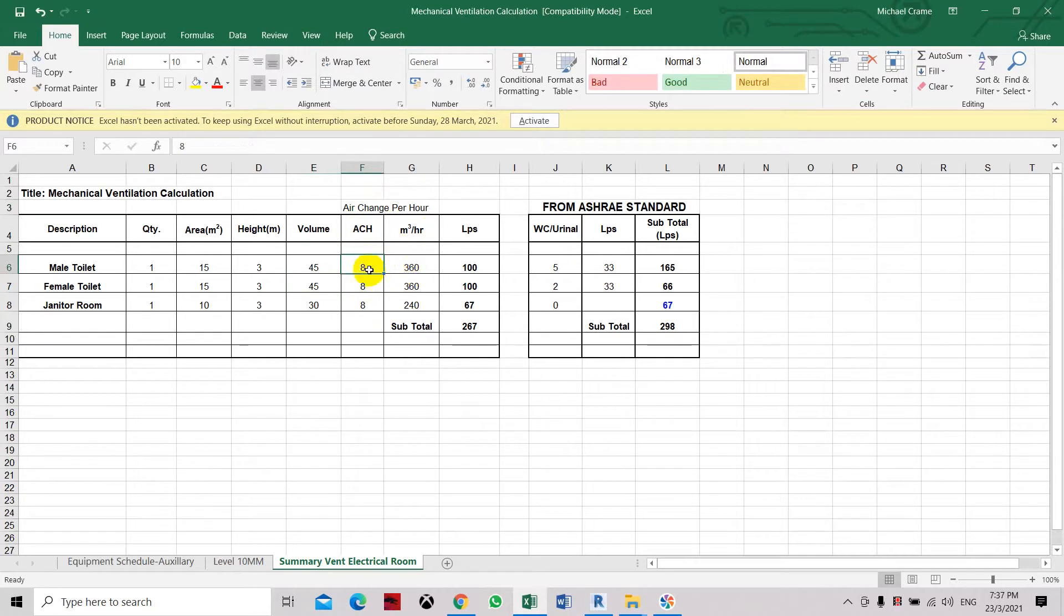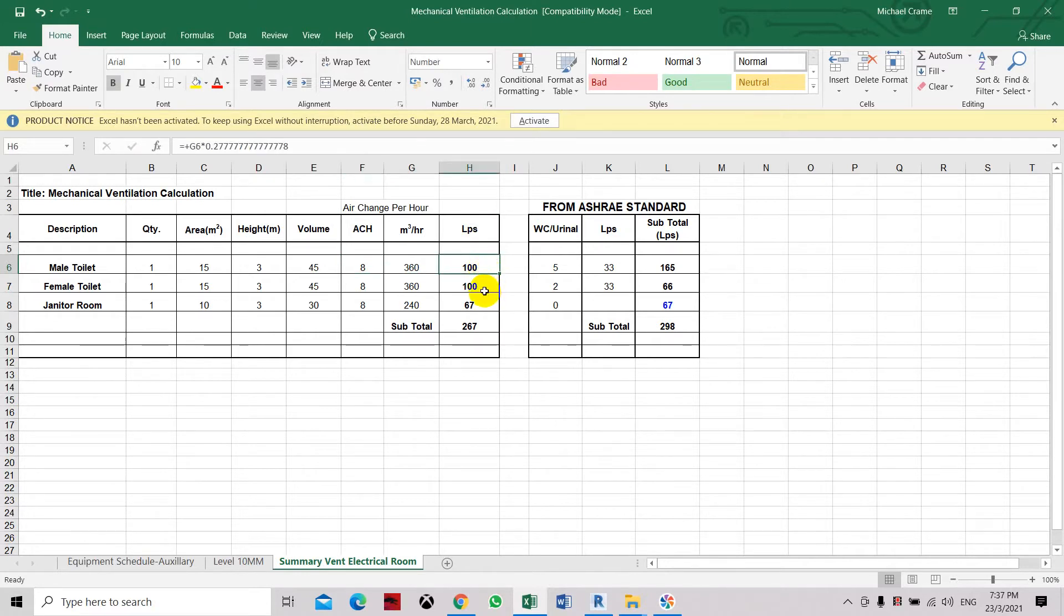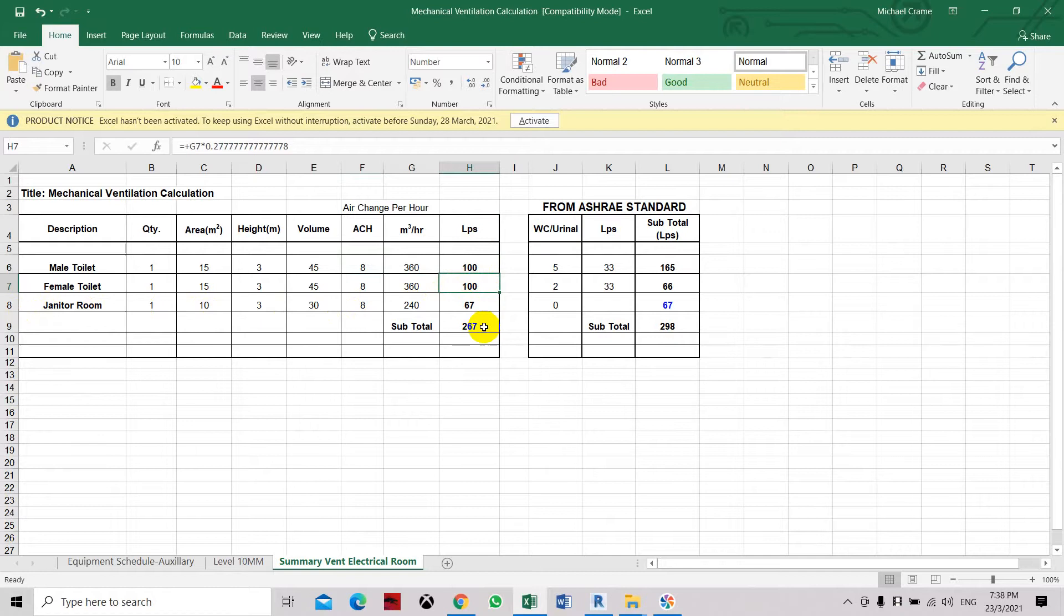We multiply volume times 8. This one will come up with cubic meter per hour. And typically we have the air flow at liters per second. So it's about 100 liters per second for the male and female toilet, and another 67 for the janitor. So in total it's about 267 liters per second.